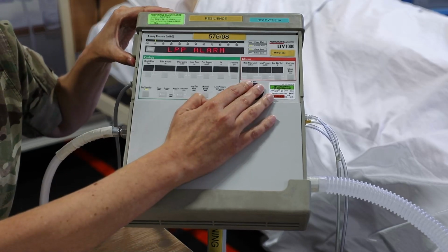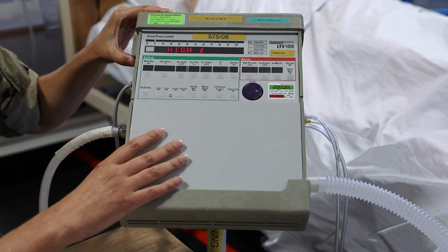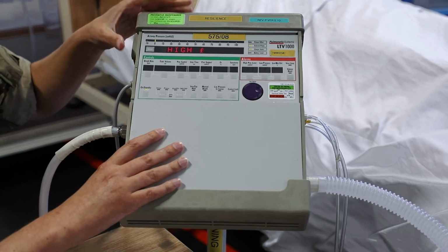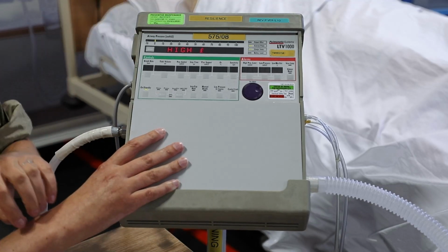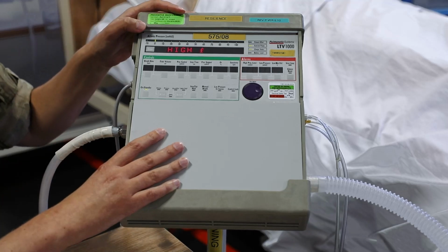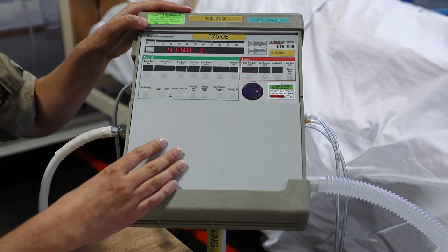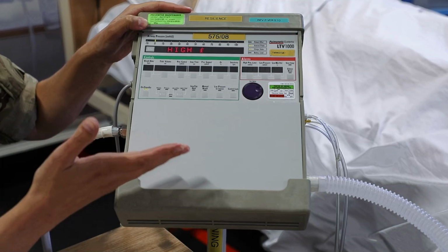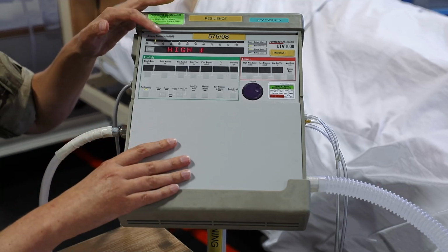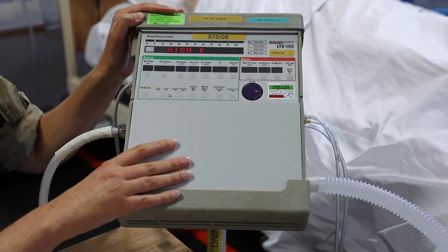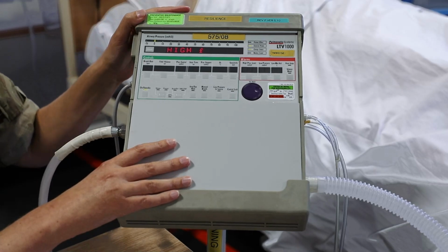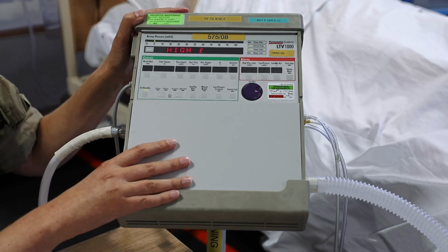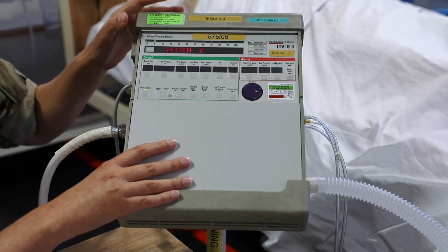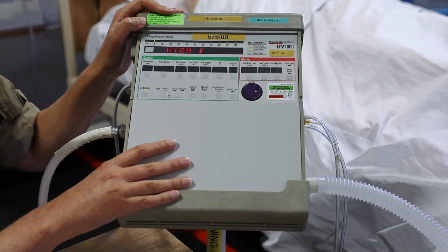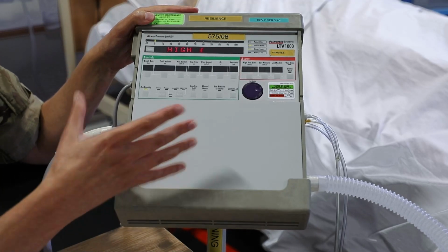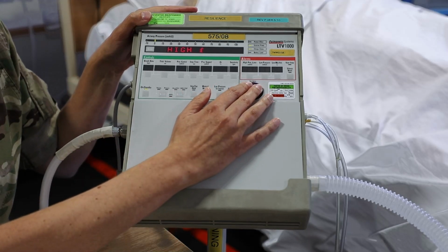Press select again to go to the upper menu, turn the dial to the right, and we get to our high frequency menu. Here you can set this specific to the patient, and you can set whatever frequency you think is suitable. So what this is going to do is if you set it at 30 breaths per minute, for example, but the patient breathes at 35 breaths per minute, it will alarm at you to tell you that you have a high frequency. So you can go into that menu and adjust it, but for this we're just going to move on.